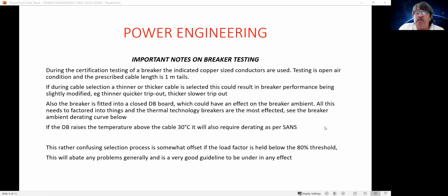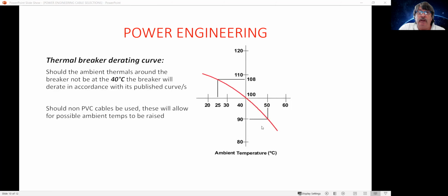Sometimes there's a rule of thumb being provided, and some wiring codes actually do specify this. This can all be rather confusing to somebody that's trying to get the right cable out and not really understanding the direction of this. So some of the wiring codes say a circuit breaker should never have 100% of load above the 80% threshold level, giving that variation. And this, in effect, really abates a lot of the problems that could occur due to variations in slight temperatures and cable variations, et cetera.